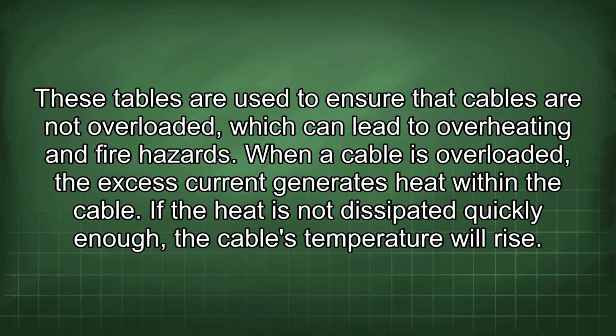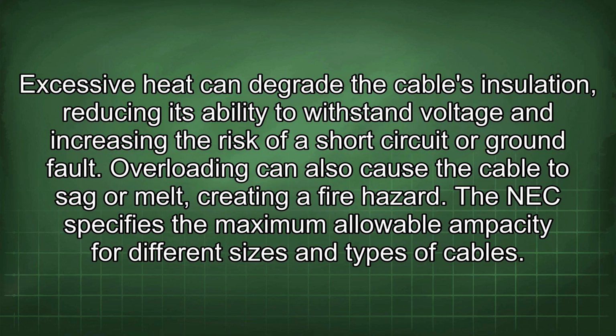These tables are used to ensure that cables are not overloaded, which can lead to overheating and fire hazards. When a cable is overloaded, the excess current generates heat within the cable. If the heat is not dissipated quickly enough, the cable's temperature will rise. Excessive heat can degrade the cable's insulation, reducing its ability to withstand voltage and increasing the risk of a short circuit or ground fault. Overloading can also cause the cable to sag or melt, creating a fire hazard.